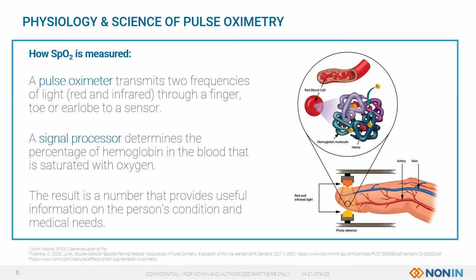So the science of pulse oximetry starts with two different light sources, red and infrared lights. These two different light sources, controlled to be on at different times, are passed through the blood, as indicated in the image shown. The amount of light that passes through is then picked up by a photodetector, where an algorithm within a signal processor then calculates the SpO2 measurement. The result of this is a number that provides useful information on the patient's medical condition. Impure light sources can shift the calibration and affect accuracy, most notably when the saturation is below 95% and/or with dark skin pigmentation. And therefore, high quality LEDs make a difference in your measurements.